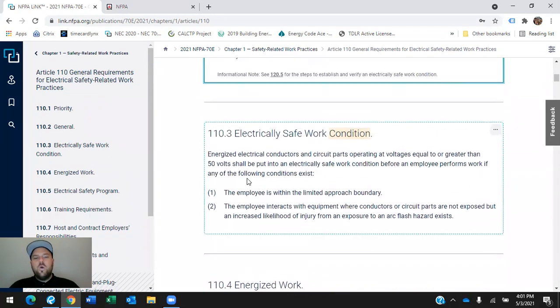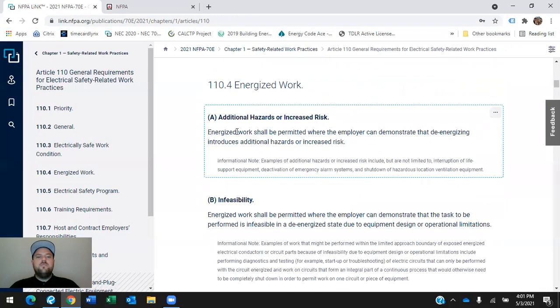Electrically safe work condition. Energized work. Additional hazards or increased risk. Energized work shall be permitted where the employer can demonstrate that de-energizing introduces additional hazards or increased risk. Sometimes turning the power off causes more hazards than leaving it on. That's what this is saying. That is when we have to put a hot suit on. That is when we have to create a MOP, a method of procedure, some way, sit down, have a meeting. I've worked on live gear.